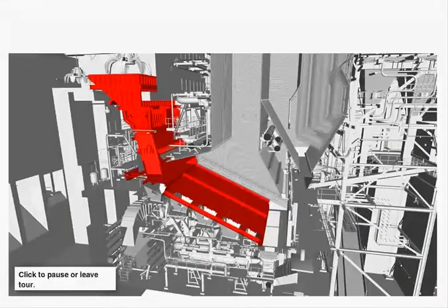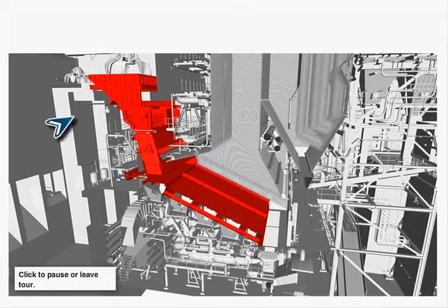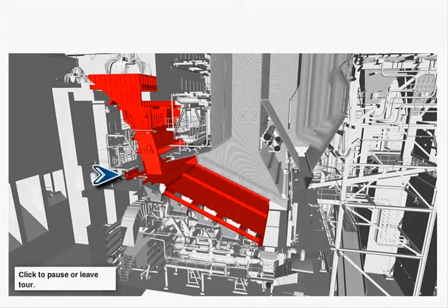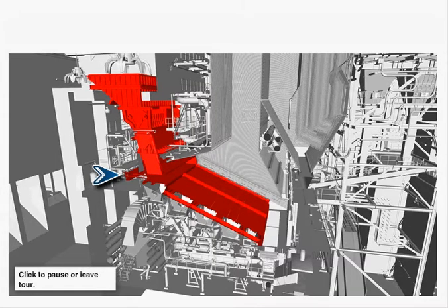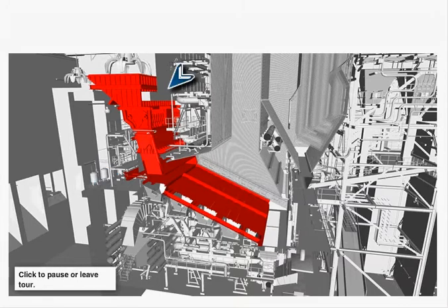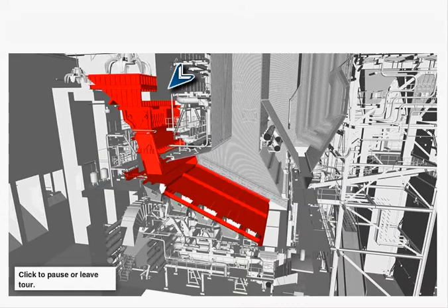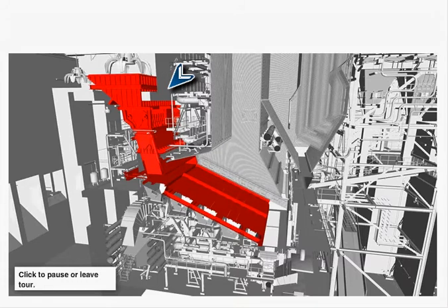For fuel feeding onto the grate we use a ram type feeding pusher. This is important because with the correct feeding we can control the combustion and energy production. The fuel rate is controlled by our automatic combustion control system. The feed chute is water cooled and made of strong steel plates. The chute is equipped with two hydraulic dampers that ensure plant safety during start up and shutdown.